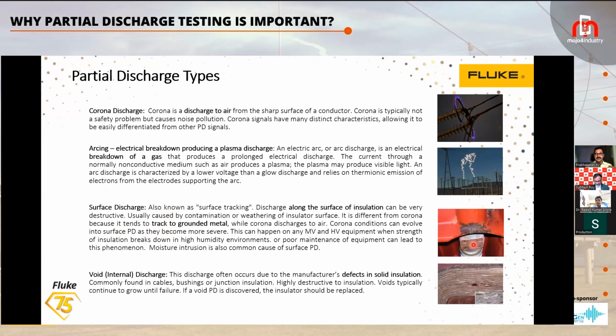And voids, this basically happens because of insufficient insulation or manufacturing defects, or if some internal damage is happening in the insulation material. Usually you will not be able to find it with your naked eyes. It may happen inside, and there can be a void, and these electrons start jumping from one end to the other end. Usually the insulation and resistance make a capacitive effect, and this capacitance comes down or increases. There can be high current pulses jumping through these voids. And this also you may not find, but when this is too much and it breaks down, you will find the entire insulation is broken down, and it can lead to some kind of fire accidents.